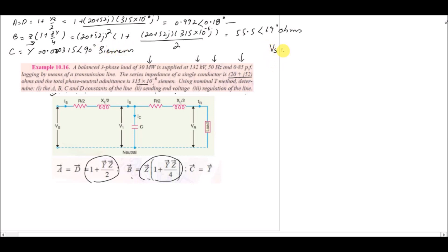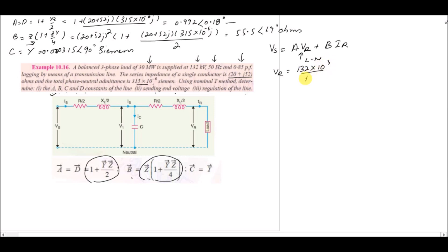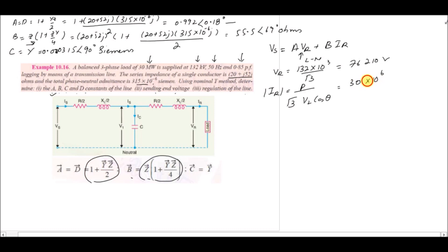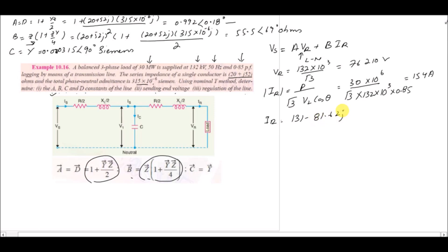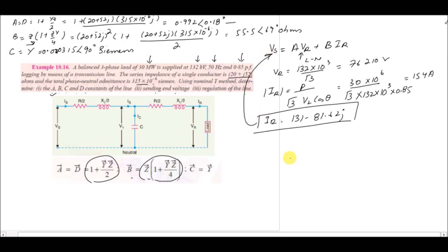To find the sending-end voltage, Vs equals A·Vr plus B·Ir. The line-to-neutral receiving-end voltage Vr equals 132×10³ divided by √3, giving 76,210 volts. The receiving-end current Ir equals P divided by (√3 × VL × cos θ) equals 30×10⁶ divided by (√3 × 132×10³ × 0.85), giving 154 amperes. Accounting for the lagging power factor, Ir equals 131 − 81.62j amperes.